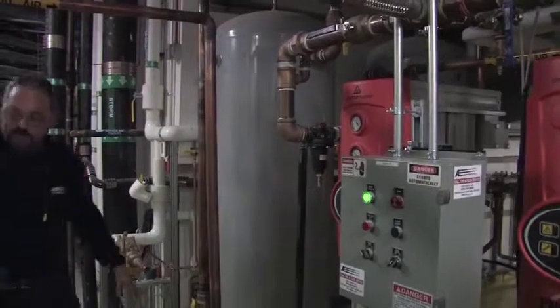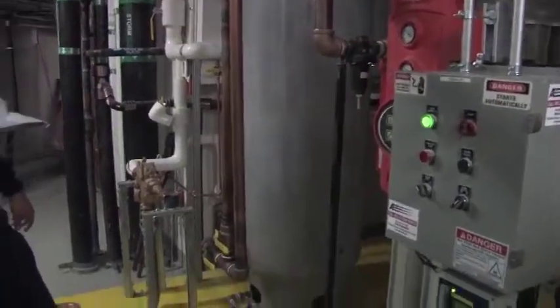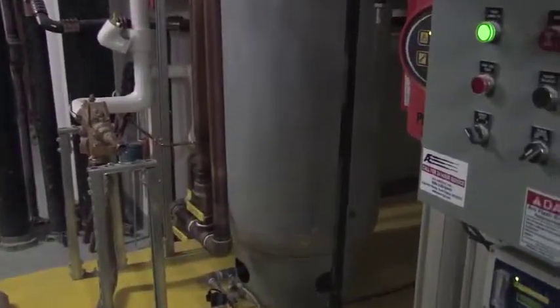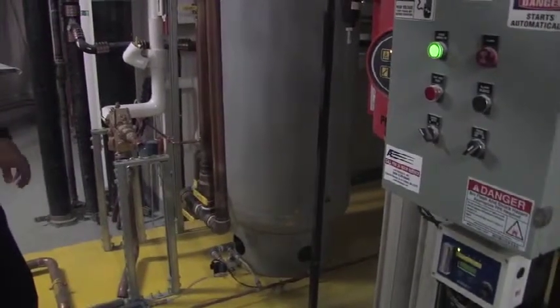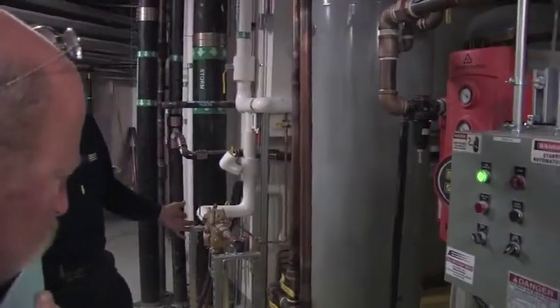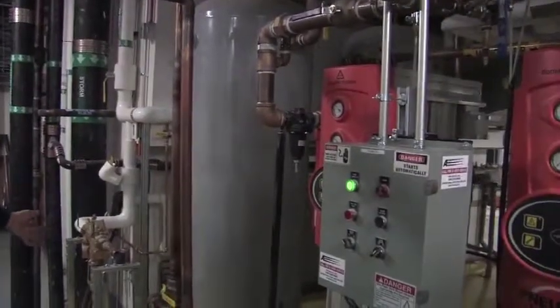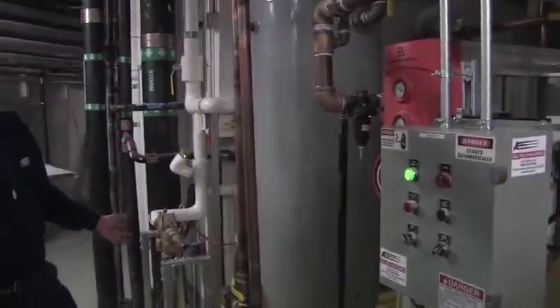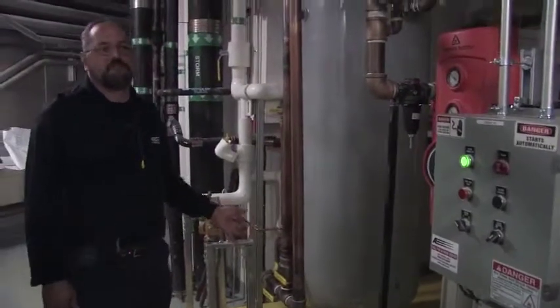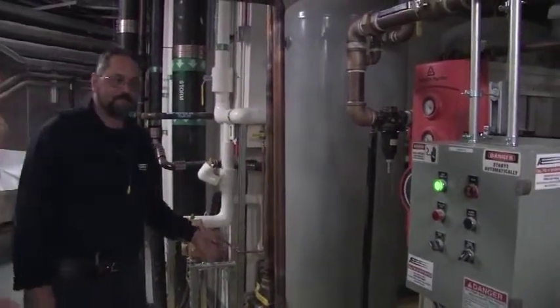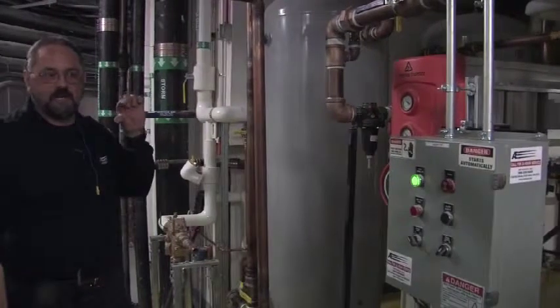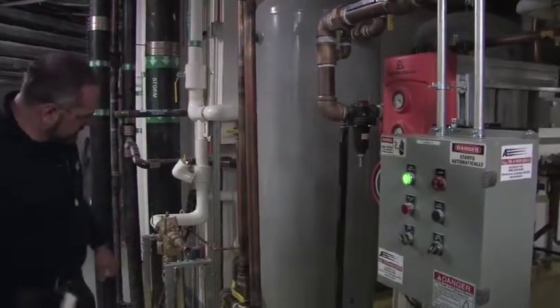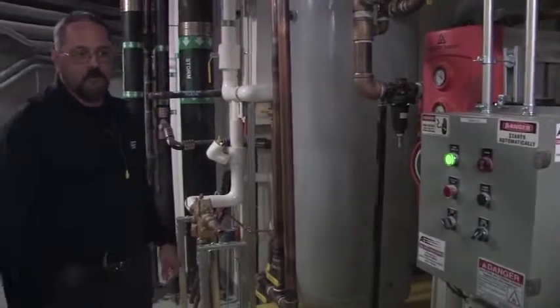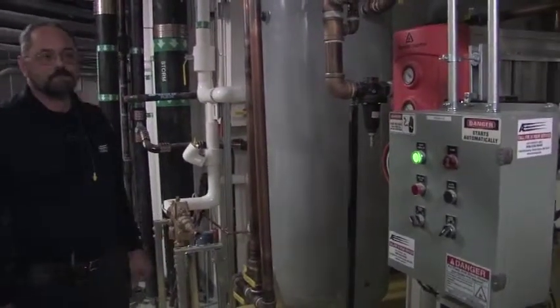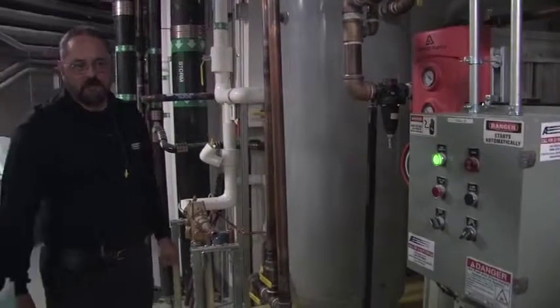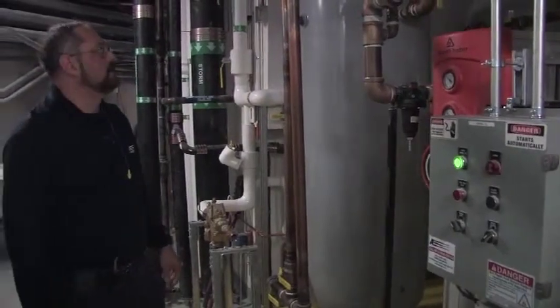Each tank has an electric automatic drain on it. There's two set points on those, one for how often it'll fire and one for how long it stays open. I was in a place last week, they put in a 3,500 gallon wet tank. So they want to run the system on a real tight deadband. Only problem is they took the same drain they had on their old 400 gallon tank, put it on and never changed the adjustment. You're getting water everywhere right now.